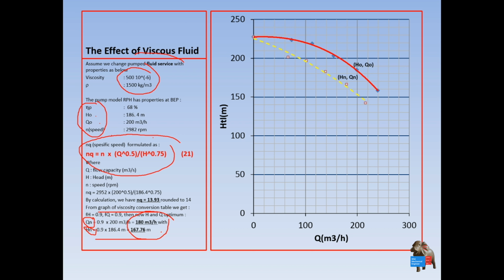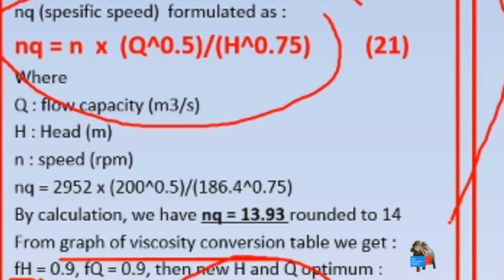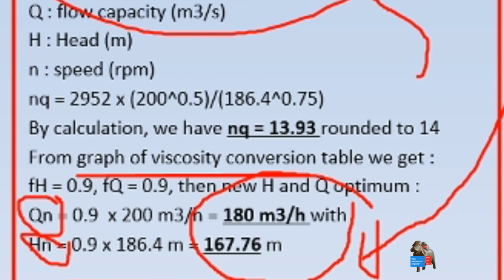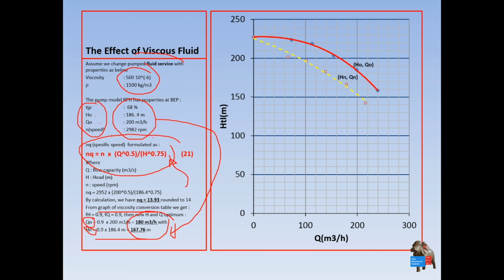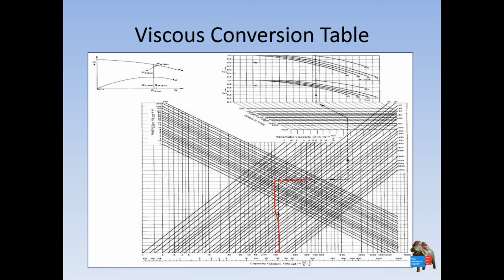Let's say the fluid is more viscous, so it sticks to each other more. When you have this performance from the lab that was tested with water, with another more viscous fluid you will have different numbers. So you have to follow this formula, but it is a bit complicated, though there is actually a chart. You move from this direction to this direction and to this direction, but we can forget it for a while, because this chart is more needed after you test the pump, and then you ask the suppliers what fluid will be transferred by this pump, and you check if this pump is still able to meet the customer requirement.